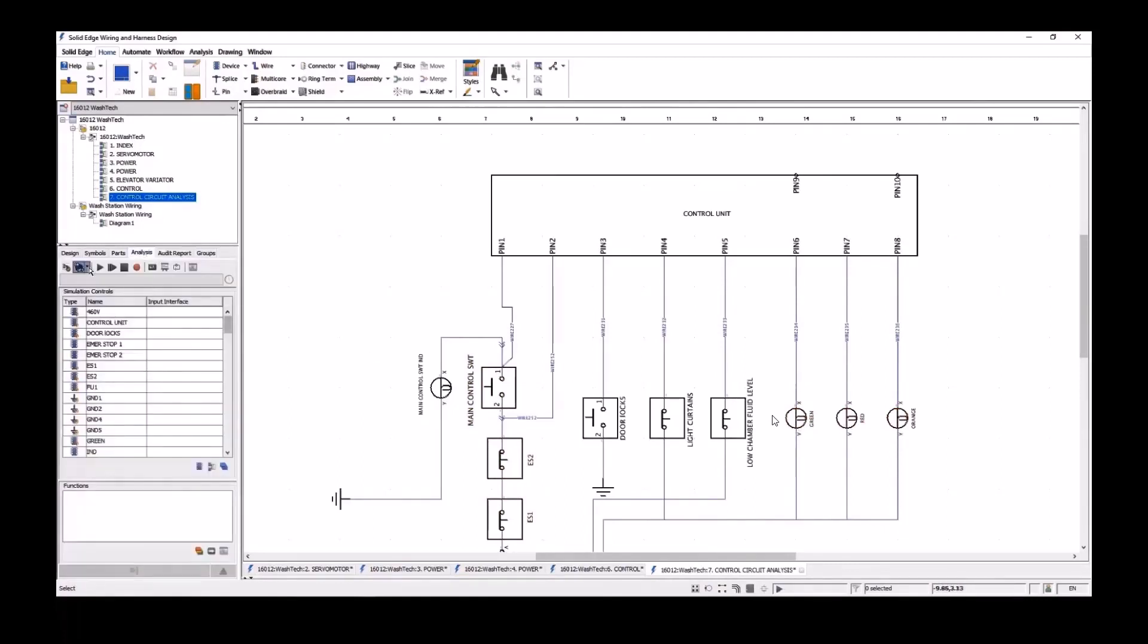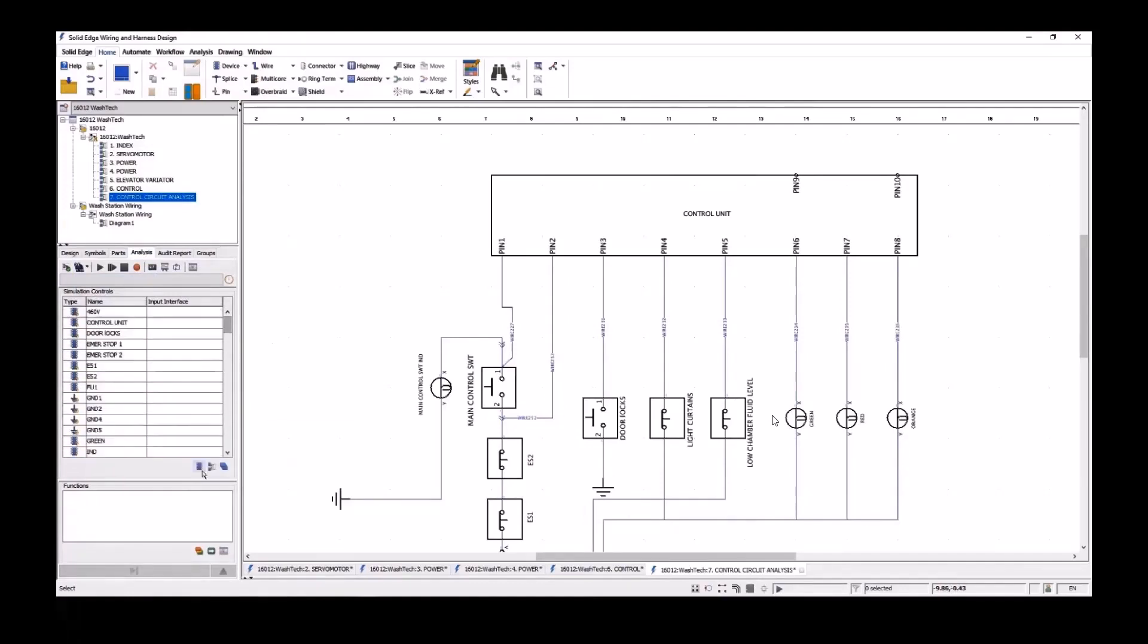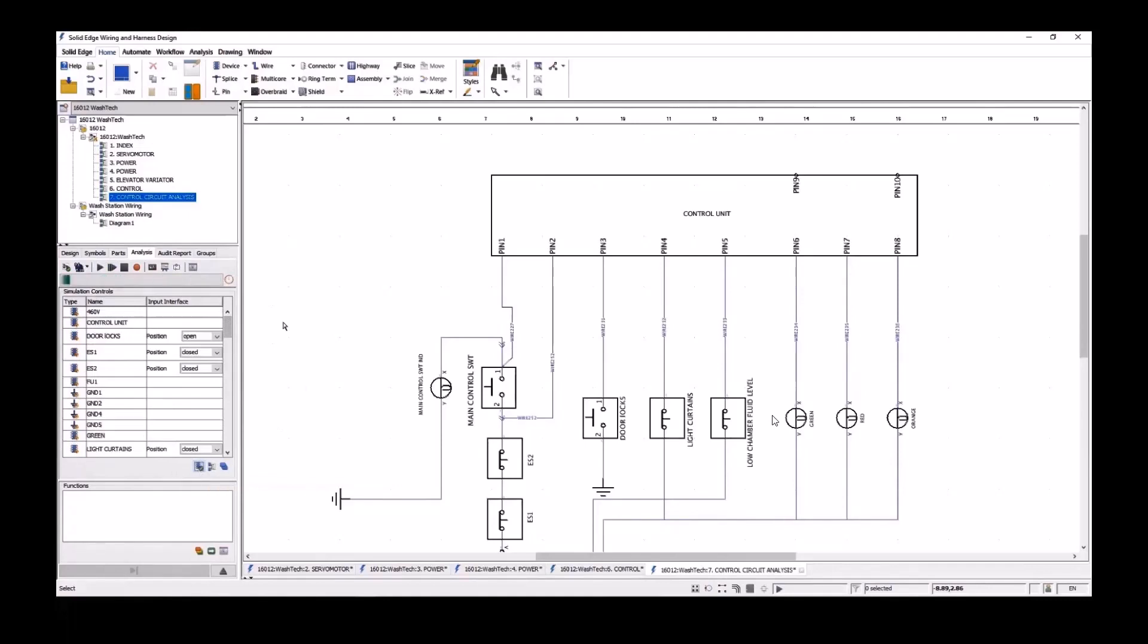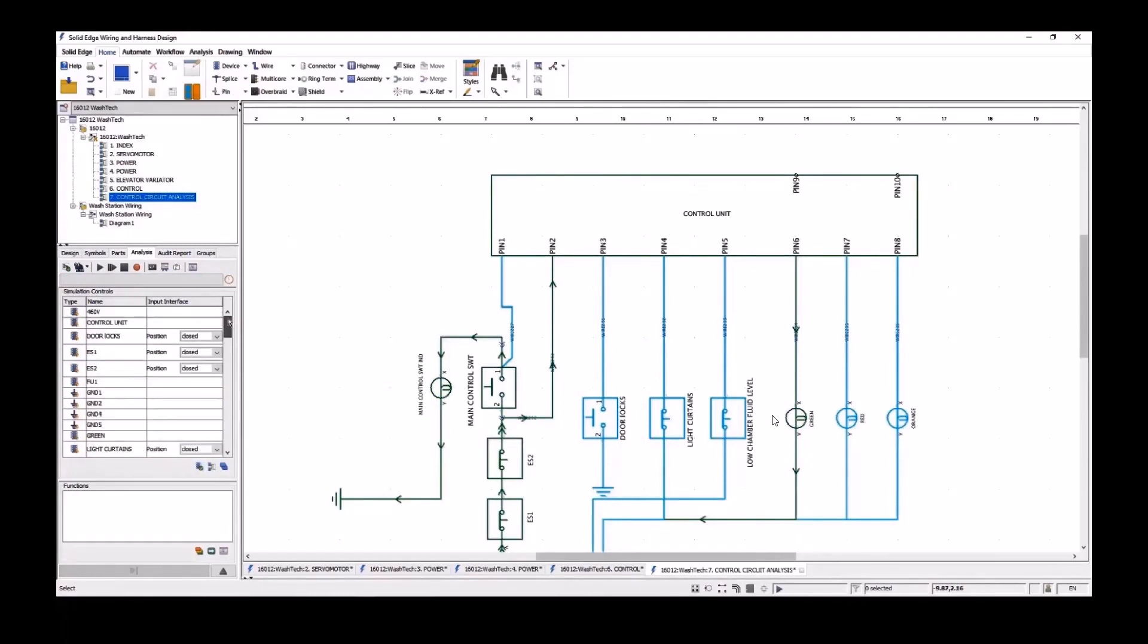In this example, we're looking at the interlocks on the doors of the wash tech machine for safety. All of these switches need to be closed before the machine will operate as indicated by the light towers red, green and orange conditions. We select the main control switch that sets the interlocks to close and we see that the green light turns on. Notice we can also interrogate each device and wire to check that it is not under or oversized to ensure an optimal integrity of the circuit.